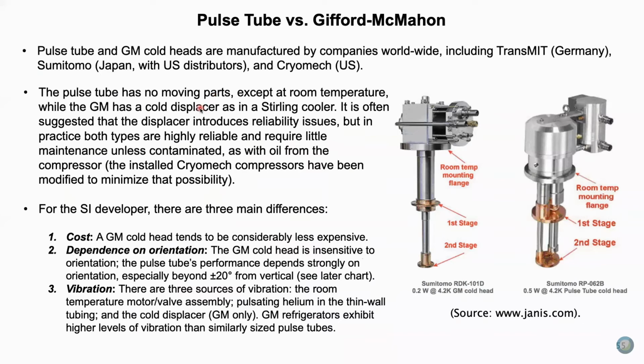So pulse tubes versus Gifford-McMahon, they're very similar, except that a pulse tube has no moving parts except at room temperature, while the Gifford-McMahon, or GM, as we'll call it, has a cold displacer, as in a Stirling cooler. It has often been suggested, at least I've heard people say this over the years, that the cold displacer introduces reliability issues, but I'm not sure I believe that's true. Both types are very reliable and require little maintenance unless they get contaminated, as with oil from the compressor. And the installed Cryomech compressors have been modified to minimize that possibility.